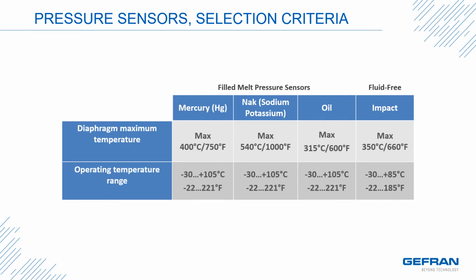Once you've chosen a sensor type based on the properties exhibited by the compound as mentioned in the previous slide, then we have to look at the maximum temperature that the diaphragm is going to see in the process. And then, of course, the operating temperature is the temperature range of the electronics housing, and we offer a number of different mechanical variations to ensure that the electronics housing can be mounted a safe distance from the temperature to keep it within the operating temperature range specification.